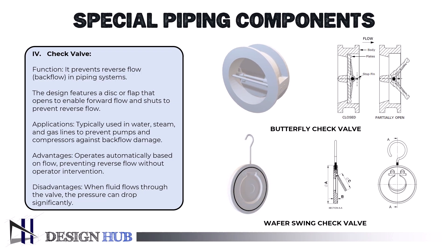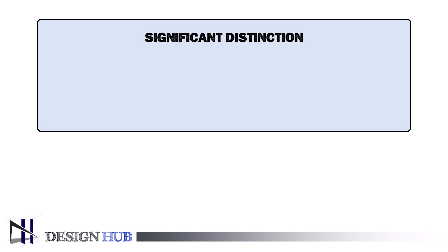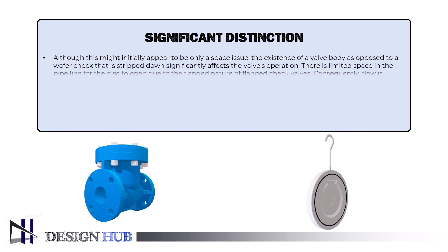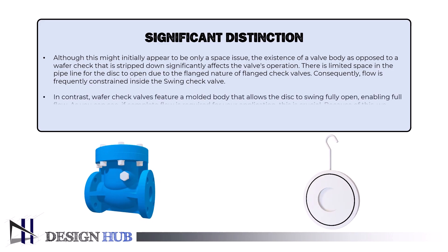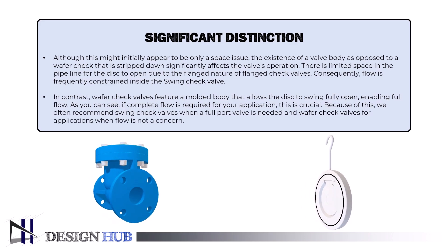Wafer check valves regulate flow via a swinging disc. Due to their compact shape, they can be installed in locations that are too small for flanged check valves to function. The disc opening region of wafer check valves is surrounded by molded bodies. The most significant distinction is that flanged check valves have limited space in the pipeline for the disc to open, frequently constraining flow, whereas wafer check valves feature a molded body that allows the disc to swing fully open, enabling full flow.